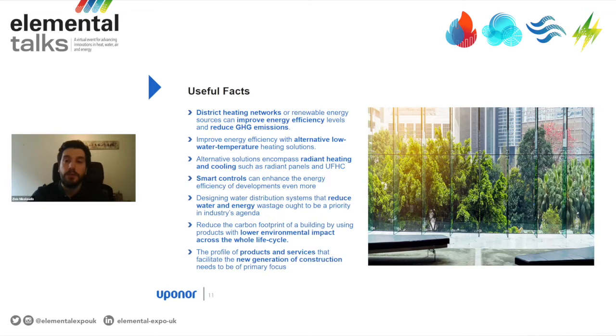In addition, overall energy efficiency can improve even more by implementing alternative heating solutions which operate at lower water temperatures, or cooling systems that operate at higher water temperatures compared to conventional HVAC systems. Some prime examples of these alternative solutions are radiant heating and cooling systems, such as radiant panels and underfloor heating and cooling. On top of that, when smart controls are combined with the above alternative solutions, they can enhance the energy efficiency of developments even more.